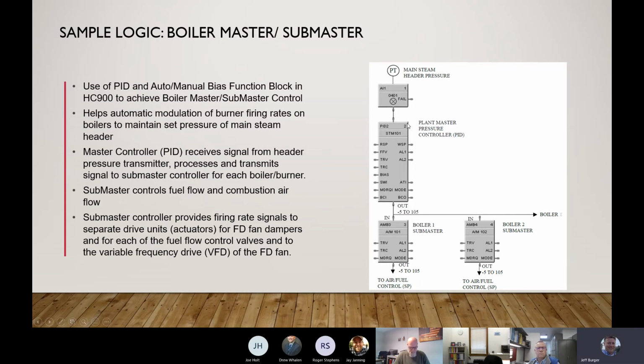And that number is a sequence order that I'm scanning. So as I program these, this might be the first function block I programmed. It has a number 1. The PID block might be the second one I programmed. That's number 2, and 3 and 4.